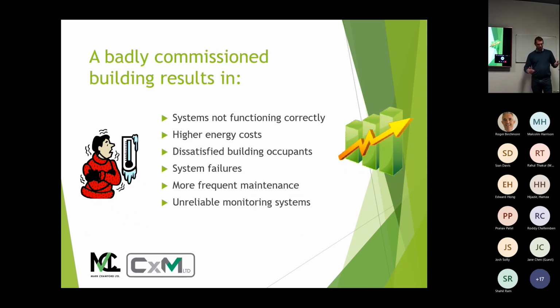So pretty much covered these, but systems not functioning correctly - so what happens if we don't commission well? They don't work properly. They really don't work properly. And it can be as simple as two rooms - the sensor there and the one on the other side of the wall go back to the same control box, and someone's got the terminals the wrong way around. So this sensor's looking at that room, that sensor's looking at this room, and therefore no one's ever happy. And it's as simple as that.